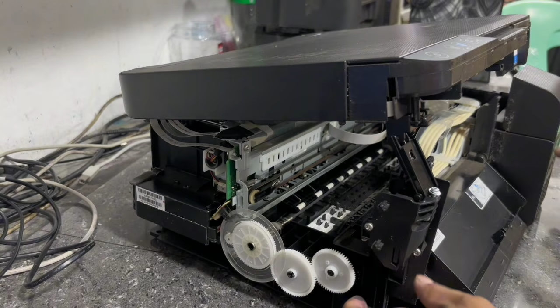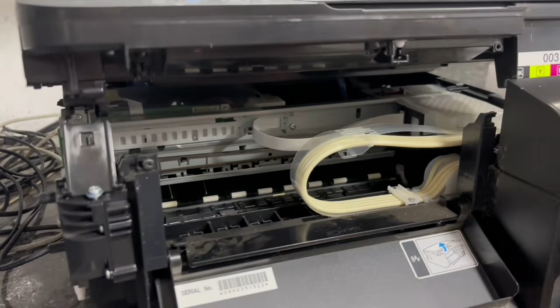Here we check the encoder disc, making sure it is properly aligned and attached to the side roller gear. Also check the encoder disc sensor, making sure it is not broken and is dust-free, cleaning it with a brush if necessary. As we can see, the encoder disc and its sensor are properly aligned and dust-free.